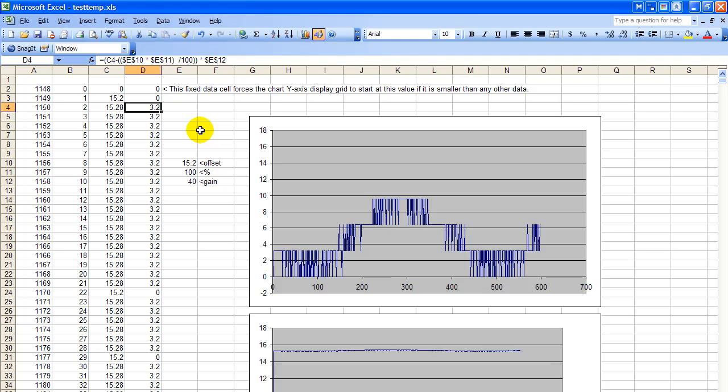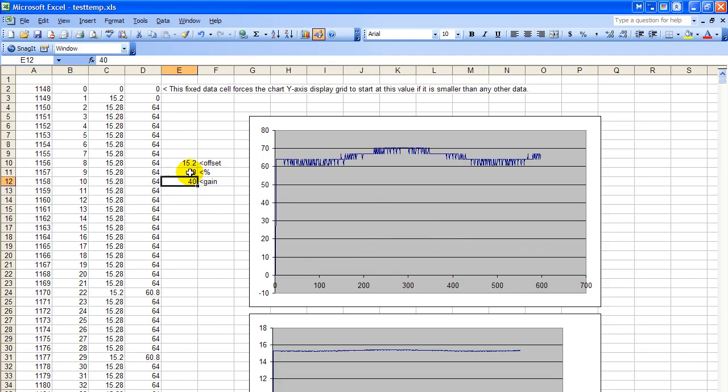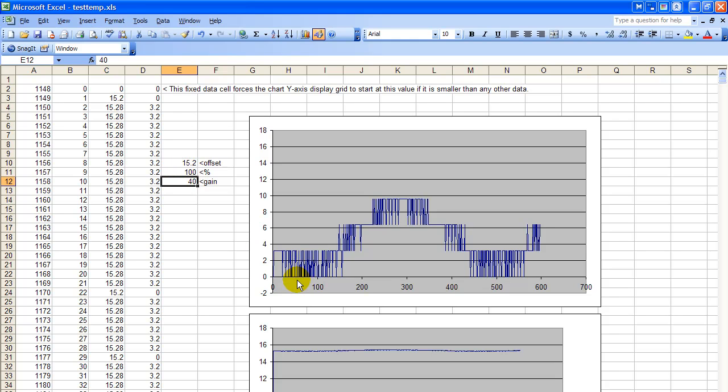So let's exercise it a little bit. If you notice, as the percentage decreases, we'll take it down to 90%. The chart climbs up and it really disturbs our results. So most times you want 100% of the offset. Here's what you watch out for. If your signal starts going below 0, then that's too much, because you start magnifying negative numbers, and negative numbers go even deeper. So it's better to keep this so that the signal never goes under 0. So let's just move it up a little bit to make sure it never goes under. We'll make it 95.5%. Well, first we'll try 90%.